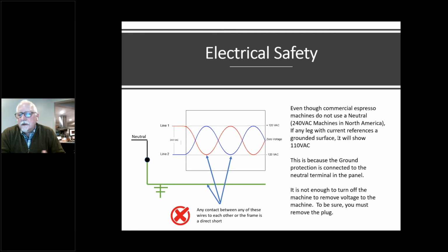So that ground protection is the overriding protection of the machine, because it's always easier for the current to go back through the ground, back to the circuit panel and blow the breaker than it is to pass through a person, because you have a little more resistance. So essentially neutral and ground are the same, but they must be kept separate for the machine to operate properly. For example, if you've got a loose neutral wire somewhere in the plug, you can't simply run that to ground and make it work. At least you're not supposed to.